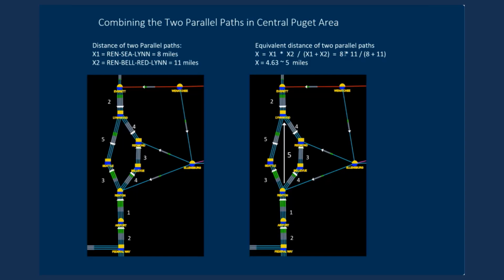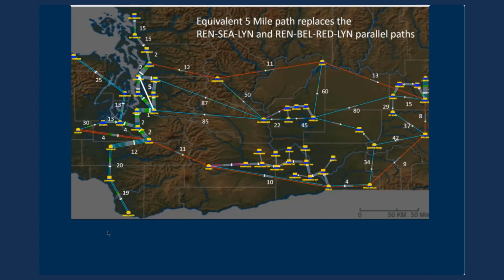So you see how that very simple calculation can be applied to build an equivalent impedance or reactance for two parallel paths. And we've actually done the combination. We combined the paths in series around this way, in series around this way, and then we took those equivalent lengths and reduced them to a single length from here to here. So we show that on our final transform map of the electrical distance diagram. We have the white arrow that says the equivalent distance in miles from Renton to Lynnwood is 5.